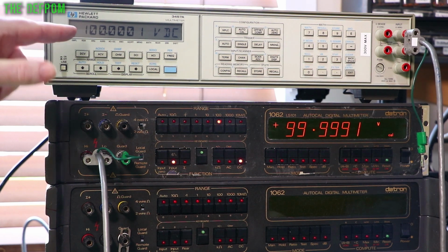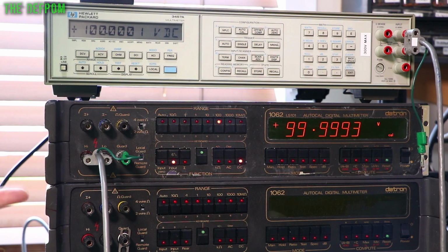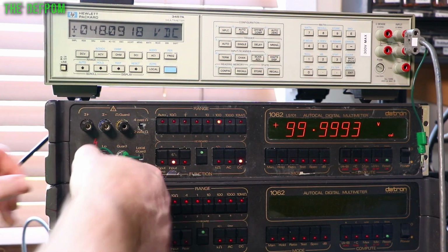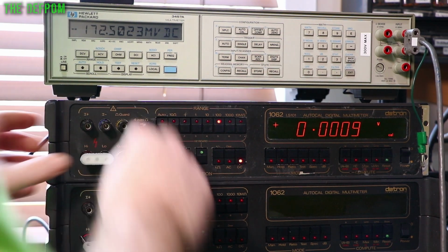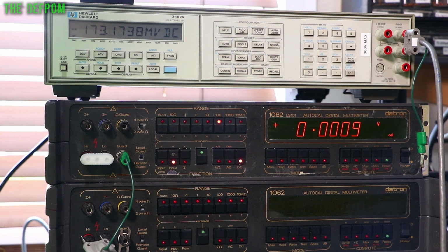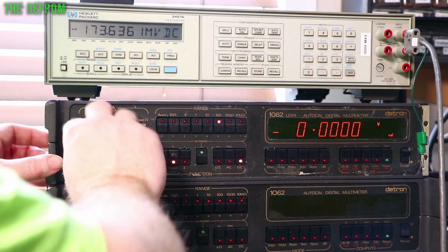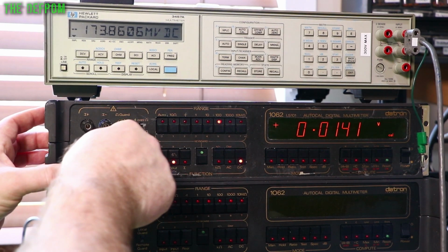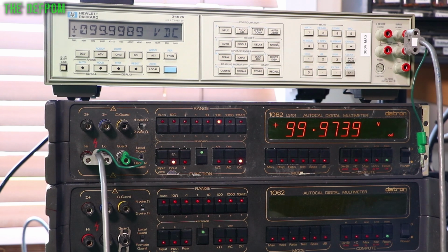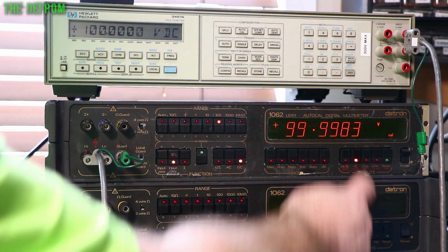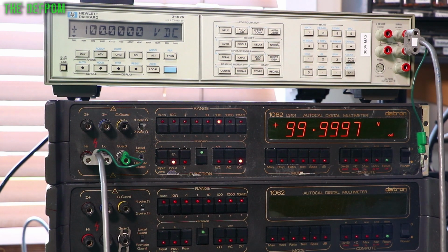So now I'm doing my 100 volt range, as you can see, get 100 volts set up on the calibrator. So I need to shut this off so I can disconnect it. Don't want to get zapped. Shut that in there. Check the zeroing. It's off by a little bit. Zero it. Okay. Shut the back in. Turn the calibrator back on. Let it stabilise again. Okay, let's do a gain. Maybe again. Okay.